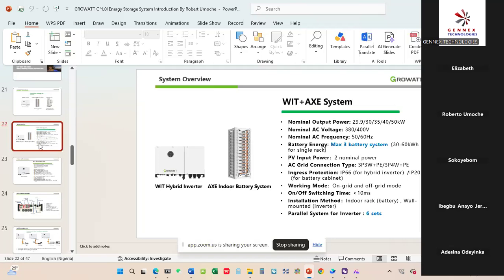Then the ingress protection for this inverter is IP66, like the others. Then why is the battery IP20? So the battery must be indoor. Then work mode, you can work on grid mode and off-grid mode. The switch time is 10 milliseconds. So what this switching time means is, maybe your system is running, there is grid present, and while your load is running, the grid power is interrupted. It is the time it takes for your system to take your load back from grid to battery mode, or inverter battery mode, like the storage mode, the backup mode.